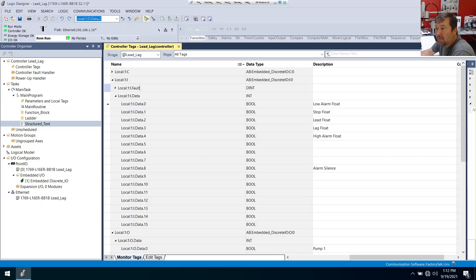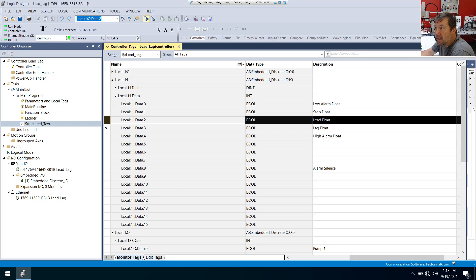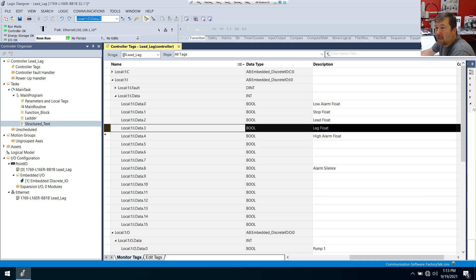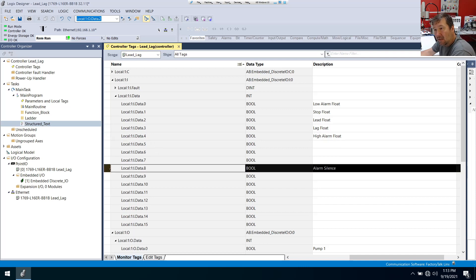But let's talk about the IO assignments that I have first. For my inputs, I have input 0 as my low alarm float. I have input 1 as my stop float. I have input 2 as my lead float. Input 3 as my lag float. I have input 4 as my high alarm float. And then I have input 8 as an alarm silence.